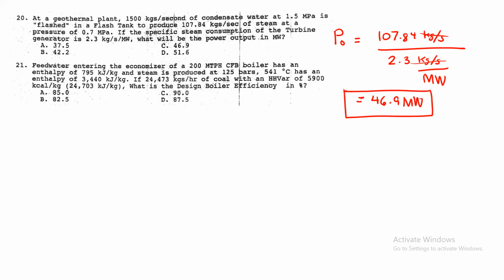So, next, 21. Feed water entering the economizer of a 200 metric tons per hour CFB boiler has an enthalpy of 795 and steam is produced at 125 bars, 541 degrees Celsius, has an enthalpy of 3440. So if 24,473 kilograms per hour of coal with an HHV of 5,900 kilocalories per kilogram or 24,703 in kilojoules per kilogram, hinahanap natin dito is yung design boiler efficiency in percent.